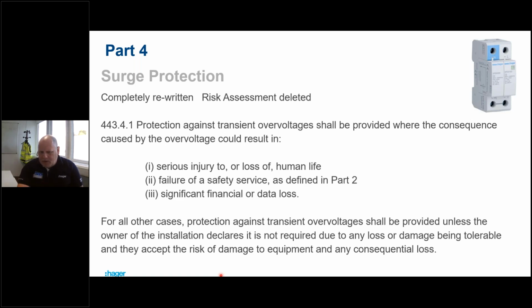Now, we mentioned failure of a safety service. Okay, so we take a domestic dwelling, we take a smoke detector. Okay, it's a wired-in smoke detector to a consumer unit. We fall into that bracket of number 2. So a domestic property, if it's got a wired-in smoke detector, we have to fit surge protection.